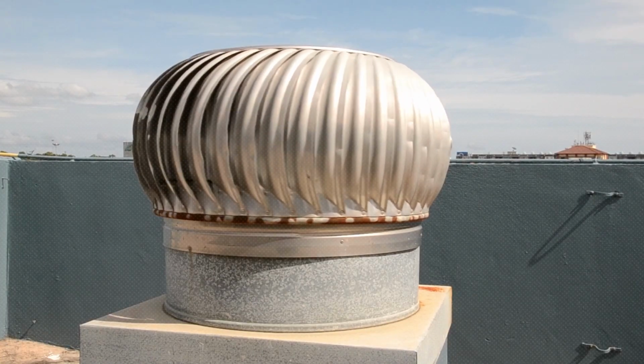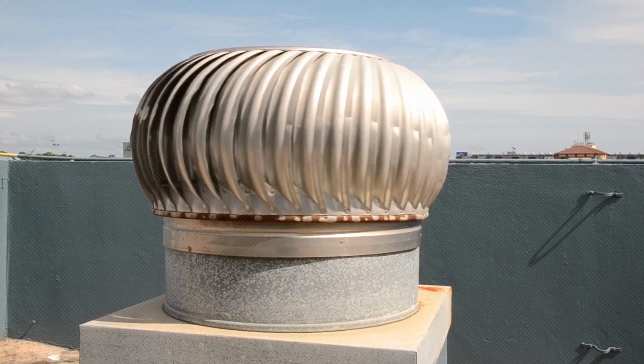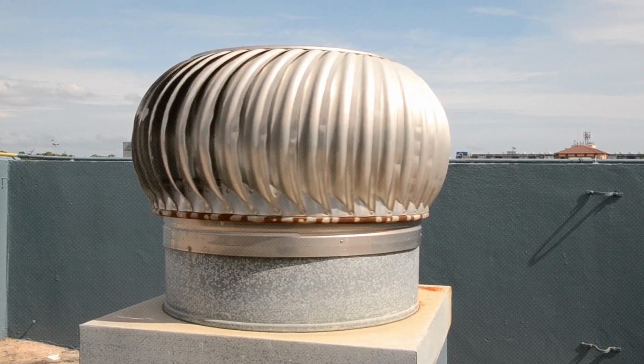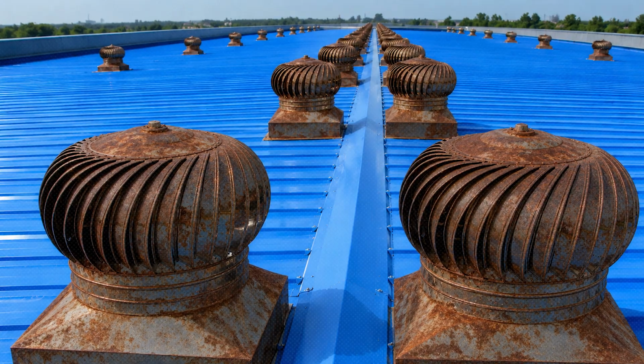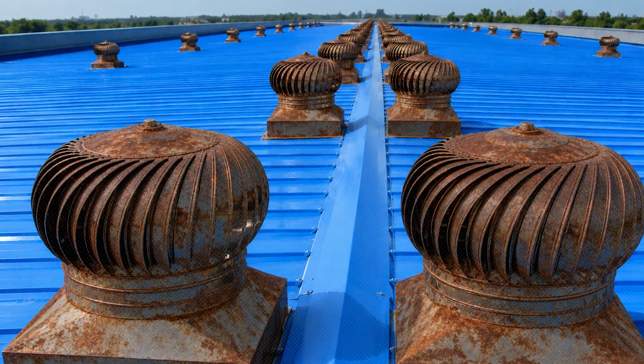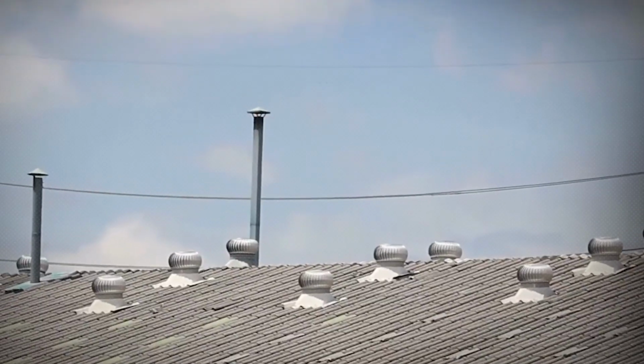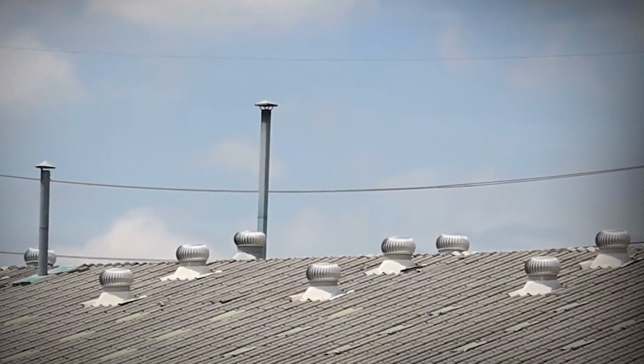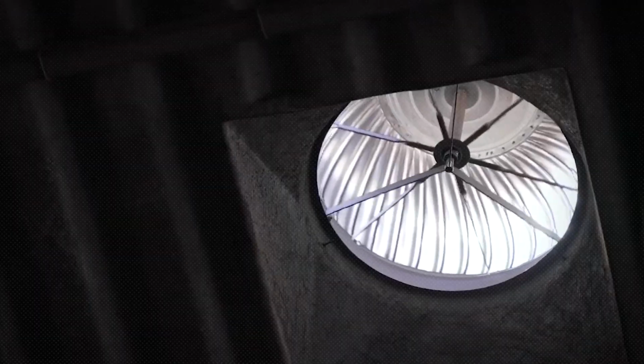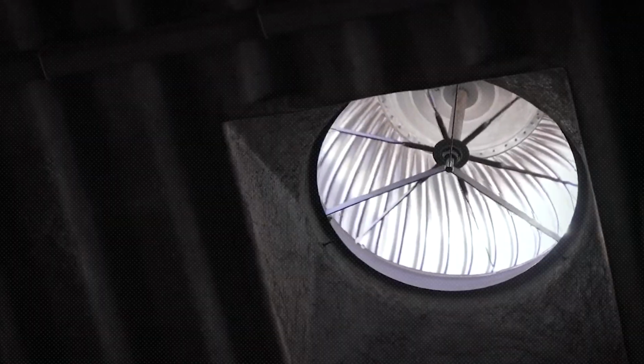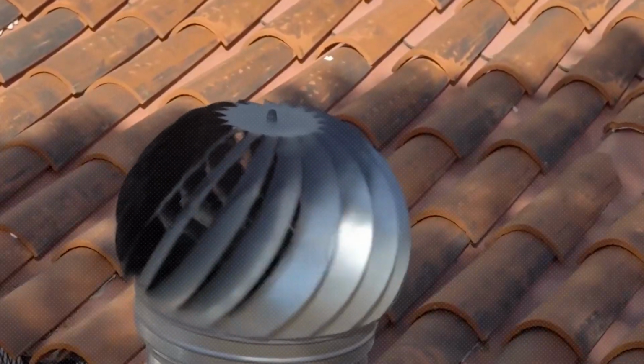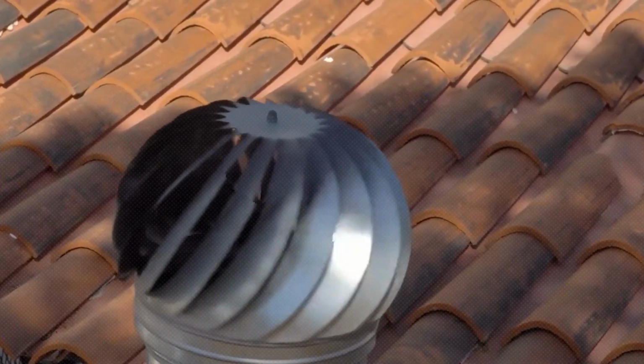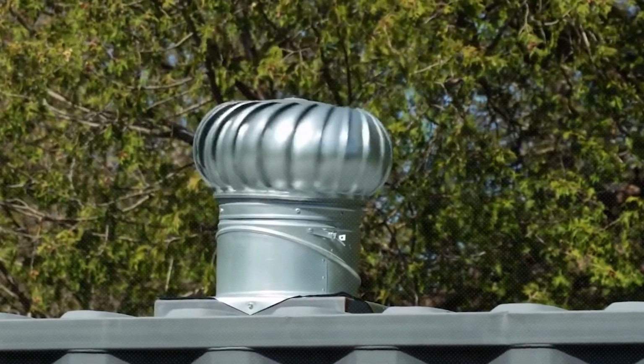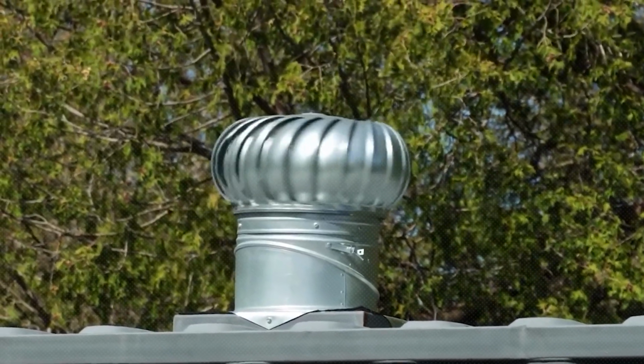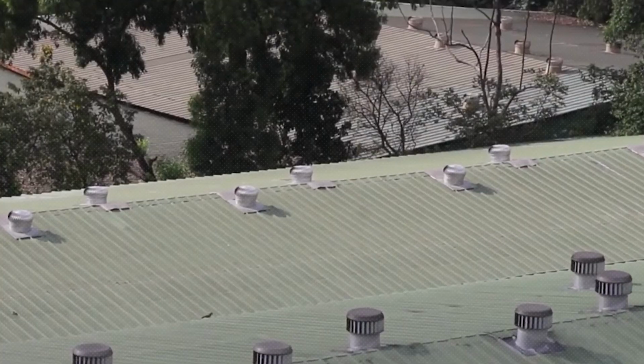Mechanical failure. The turbine's rotating head is both its defining feature and its greatest vulnerability. Ball bearings inside the unit degrade over time when exposed to moisture and dust, especially if lubrication is neglected. As they wear, they produce a squeaking or grinding sound that travels through the roof structure and becomes audible inside the home. Cheaply made units are particularly susceptible, and over years of widespread use, the turbine earned a reputation as noisy, unreliable hardware, a reputation that stuck even as higher quality versions became available.